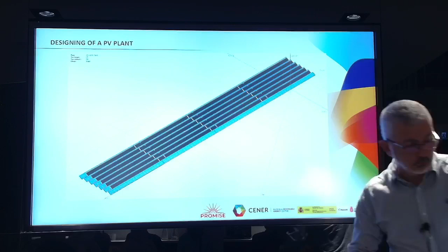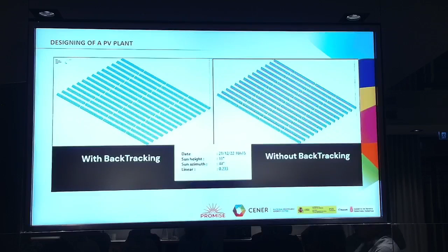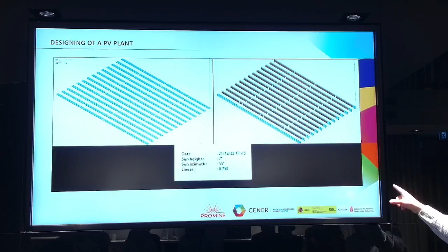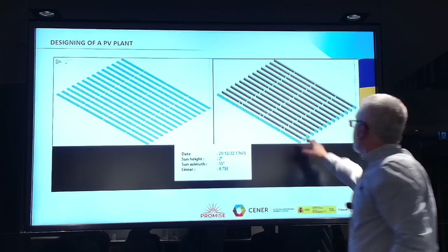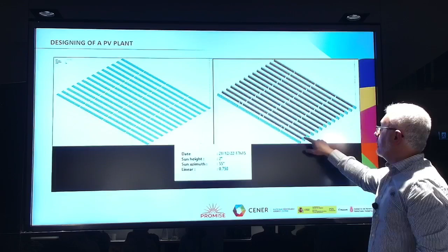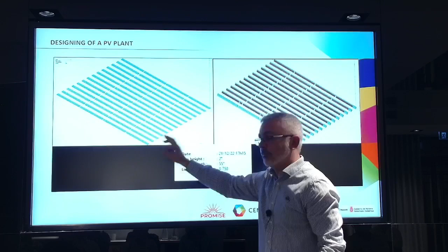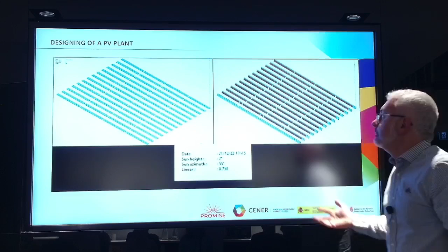For example, with solar trackers, this is a very interesting animation, because it's the same installation with a strategy with backtracking and without backtracking. Backtracking is the functionality of the solar trackers that permits not tracking at the beginning and the end of the day, in order to avoid the mutual shadings in this part of the day. So in this case, the tracking is complete, but it's generating shadings at the end of the day. In this case, the tracking is stopped, and in this way, there is not a tracking, but there is not a shading too.